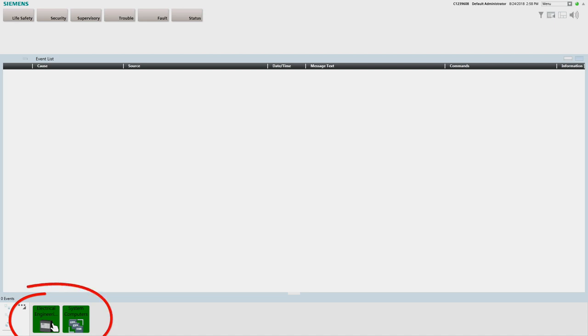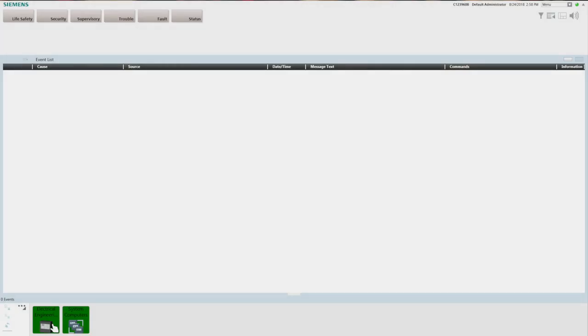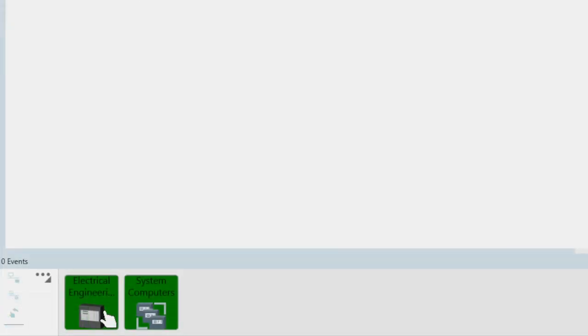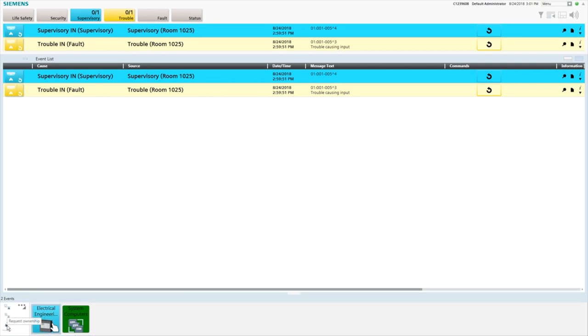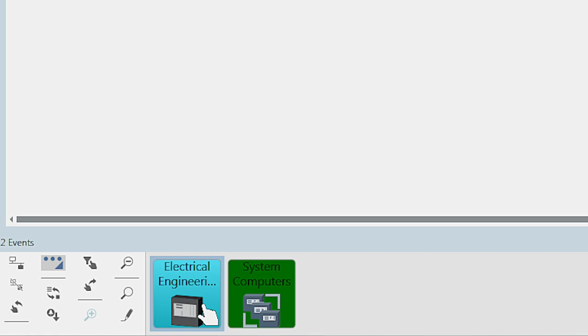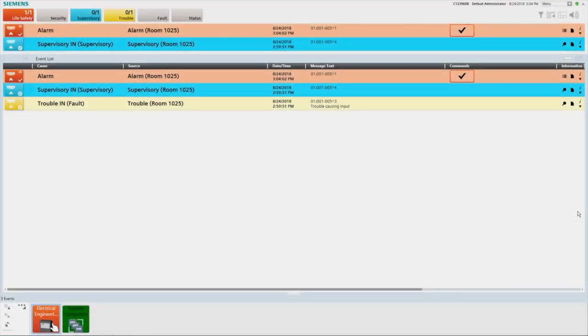At the bottom of the screen is the node map, which displays the status of each fire panel connected to the system, providing situational awareness at all times. Like the summary bar, the node map is always visible and cannot be minimized or hidden. When a connected panel is in normal standby mode, the corresponding panel icon will have a green fill. When in an off-normal state, the panel icon will have a fill color matching the highest priority event active on that panel. You can request control of a panel from another operator by selecting the panel in the node map and clicking the request ownership button in the toolbar. The node map toolbar also provides disconnect and connect, sorting and filtering, searching and zooming operations. Note that the event lamps, event icons, and panel icon in the node map will flash and the audio buzzer will sound until the event is acknowledged.